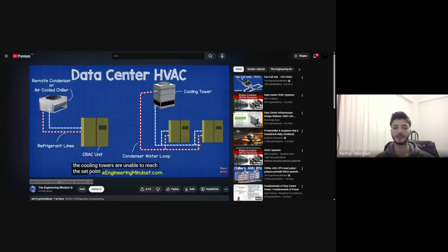Some CRAC units contain their own small individual refrigeration system, which either uses a remote dry air cooler or they dump their heat into a condenser water system. If a condenser system is used, then you'll often find a free cooler connected to the system or sometimes built into the chillers. This allows the heat to be removed without or with minimal use of a compressor, using just the fans to blow cooler ambient air across the condenser.